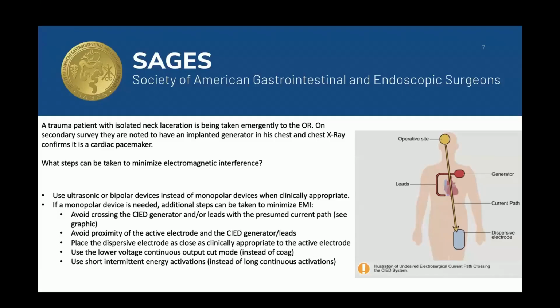And then in terms of monopolar devices, you can take additional steps by not putting the lead such that the current pathway crosses the device leads. So maybe instead of putting the device out on the hip, you could put it up on the deltoid. And that's usually a large enough area with enough surface area that you can reduce that issue. And then, like we talked about in the first section, you can use the lower voltage cut modes, and you can avoid long activations. And then you can also reduce the power output to as low as clinically reasonable, to reduce the amount of interference you're causing to the device.